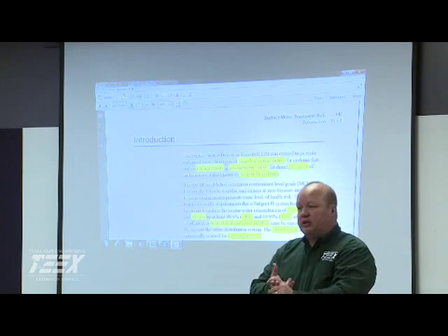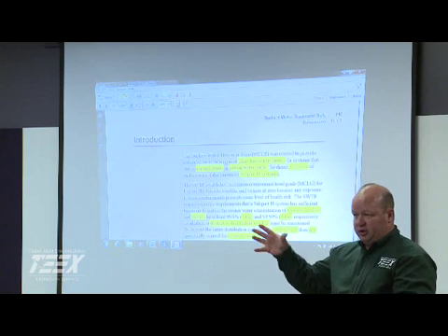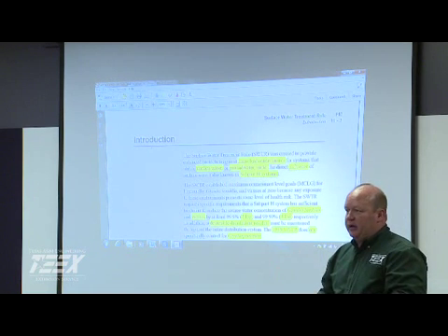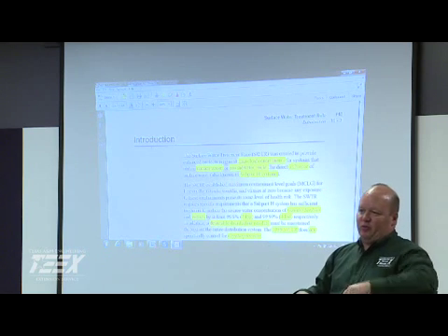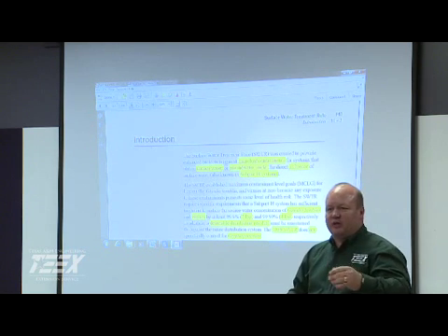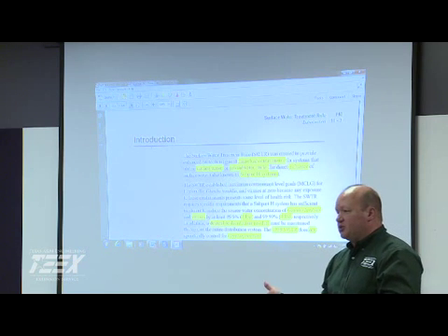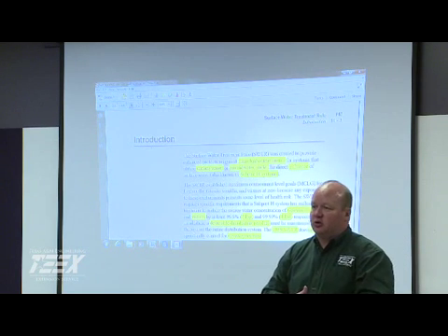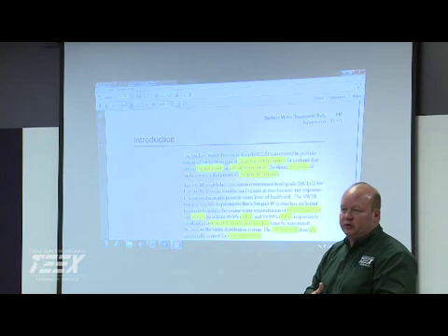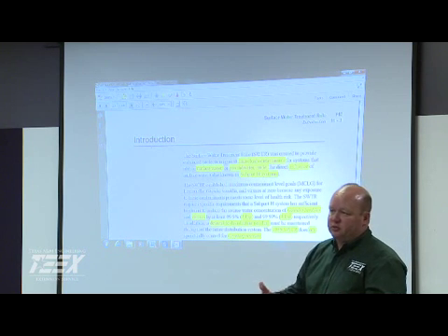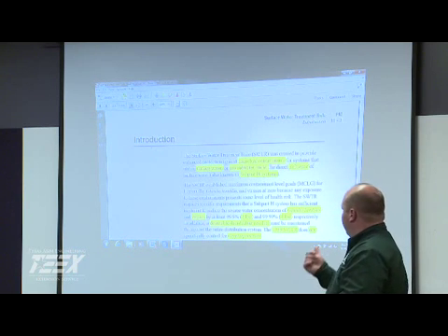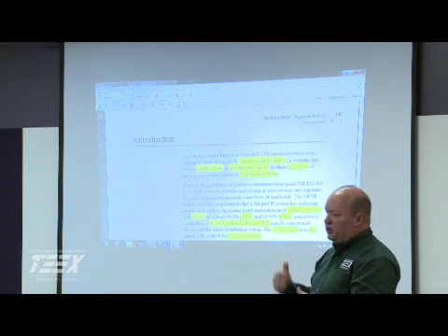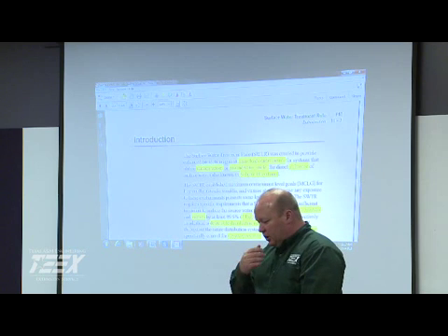Well, surface water, and then GUIs also, groundwater under the influence of surface water. And how do we know if you're under the influence of surface water? Well, every time you get a big rain, when all your parameters jump all over the place, you start getting high turbidities, pH is fluctuating, alkalinities are changing, then you're probably under the influence. Most of those are alluvial systems that are in close proximity to especially rivers. GUIs are listed under the subpart H.